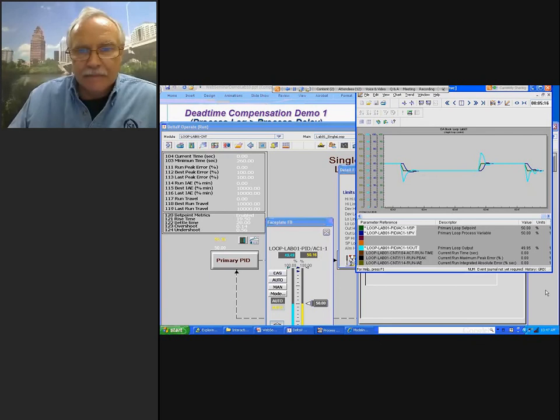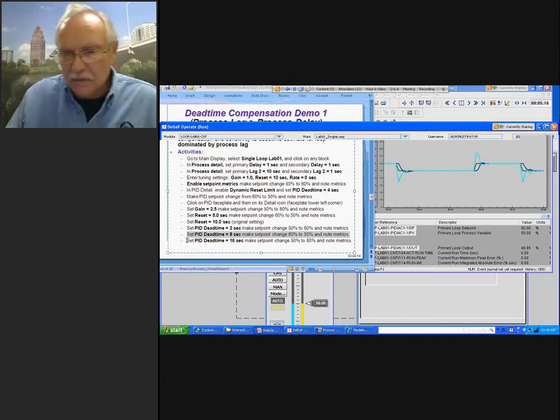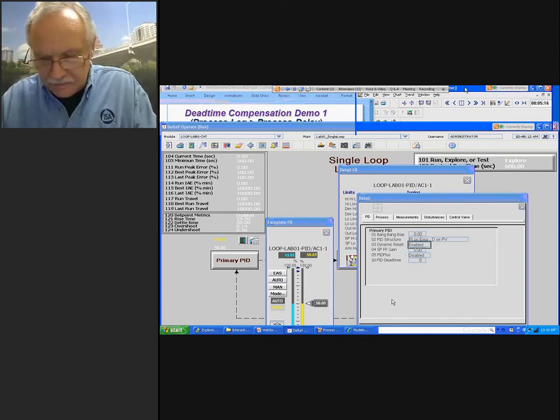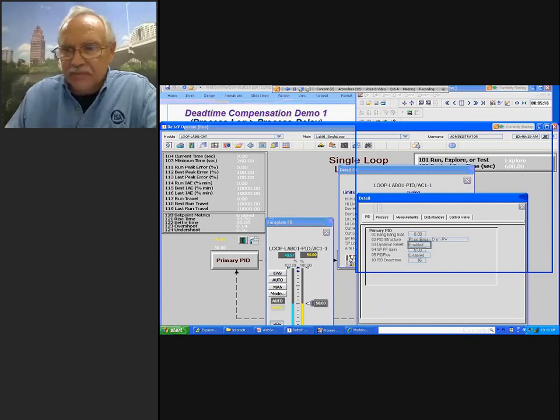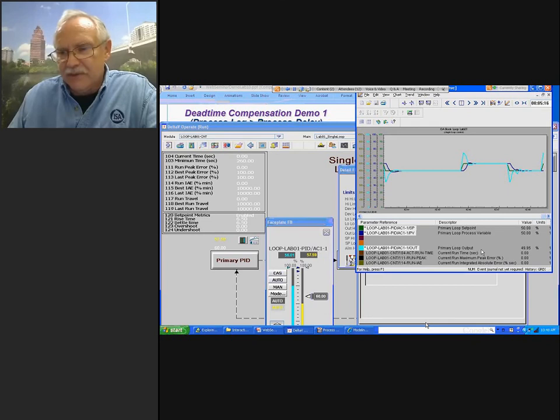Now let's make it off by 400%. So let's set the dead time to 16 seconds, and make another set point change. And it's going to get more jagged. We clearly have created a problem here.